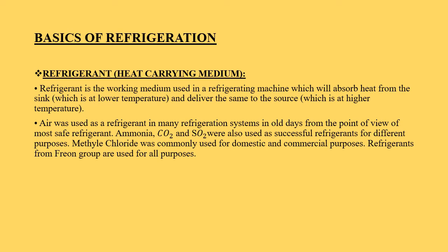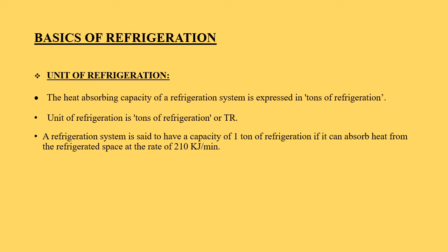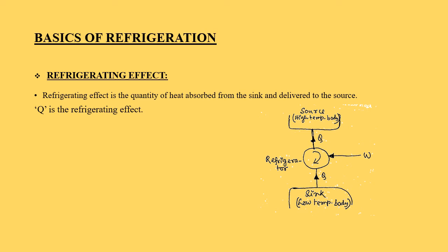The unit of refrigeration is the ton of refrigeration or TR. It is the heat absorbing capacity of a refrigerating system. A refrigeration system is said to have a capacity of 1 ton of refrigeration if it can absorb heat from the refrigerated space at the rate of 210 kJ per minute. The refrigerating effect is the quantity of heat absorbed from the sink and delivered to the source. In the diagram, Q is the refrigerating effect.